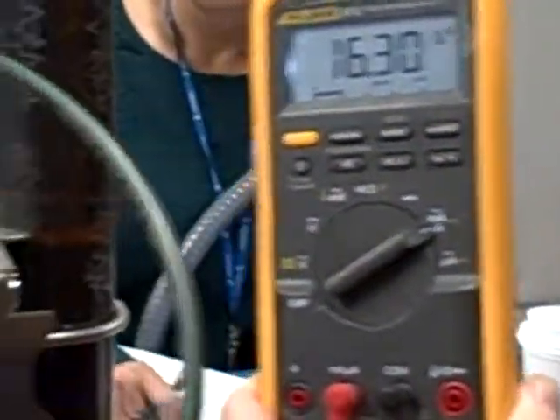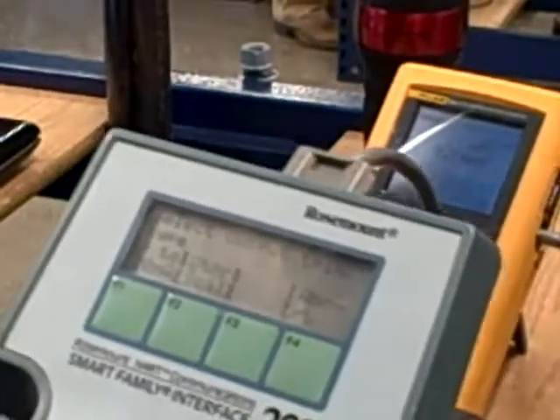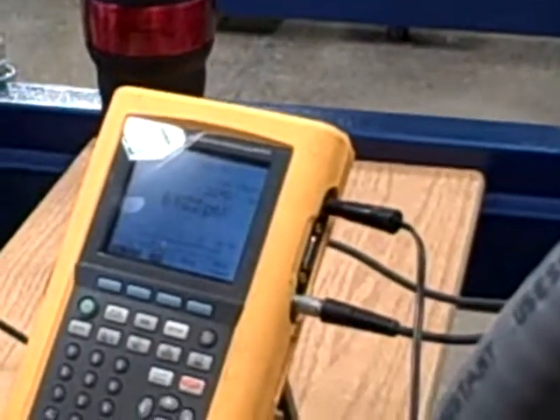Our 9.2 PSI coming in is going to give us 16.3 milliamps coming out. Remember, this was scaled, ranged to a 0 to 12 PSI range.